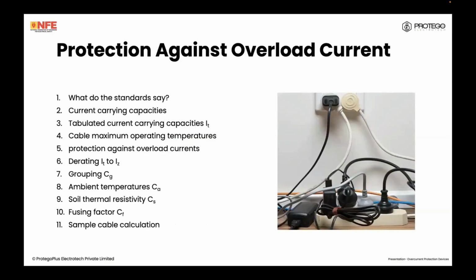So this is a very vast topic. So I'll delve into the specific points that tie in with the actual devices. What do the standards say? We look at how we calculate a current carrying capacity from a tabulated current carrying capacity, how this has to do with cable maximum operating temperatures, and how we protect against overload currents.